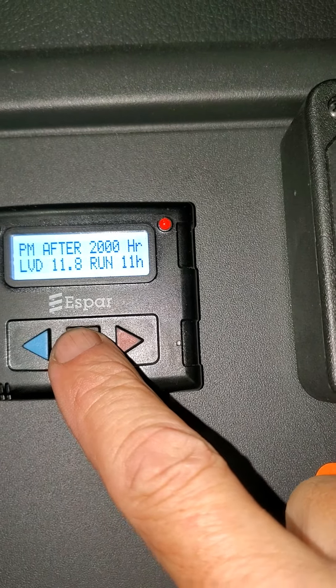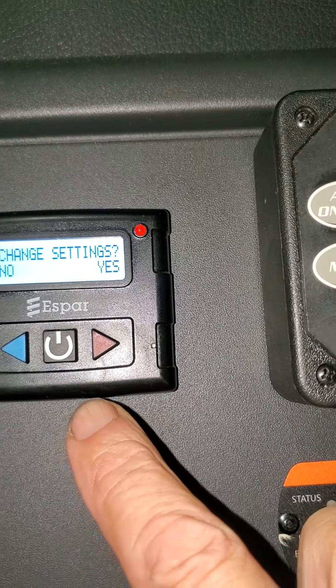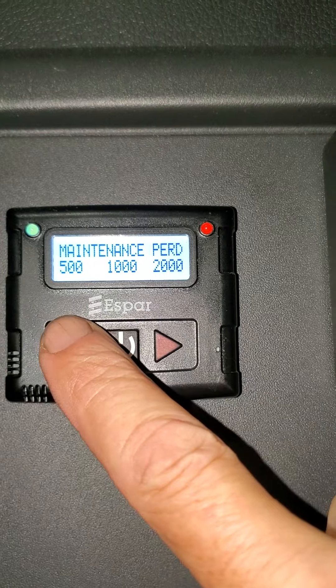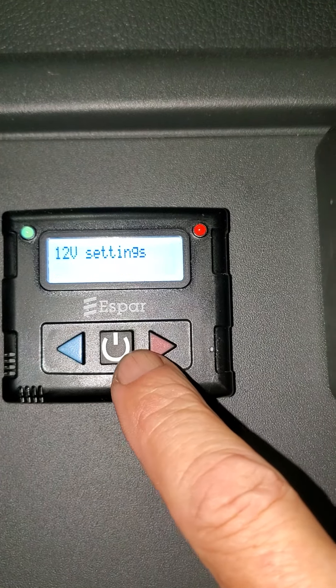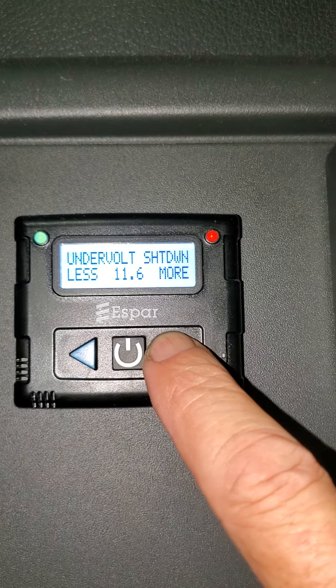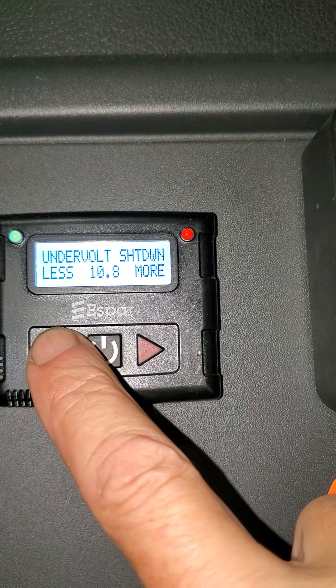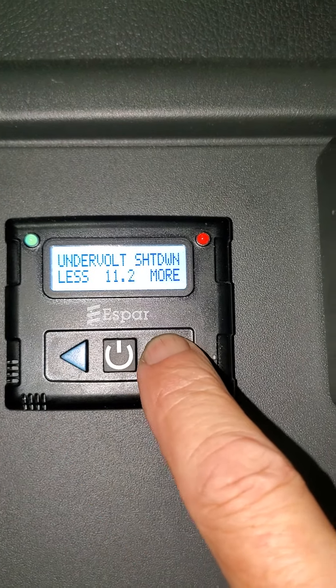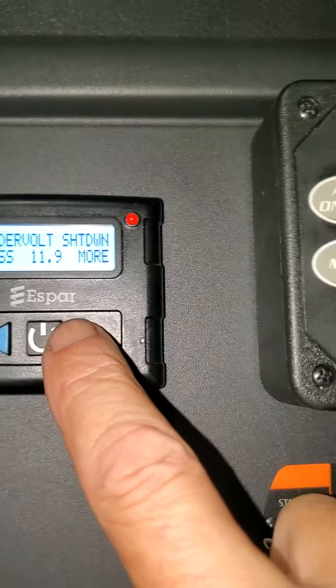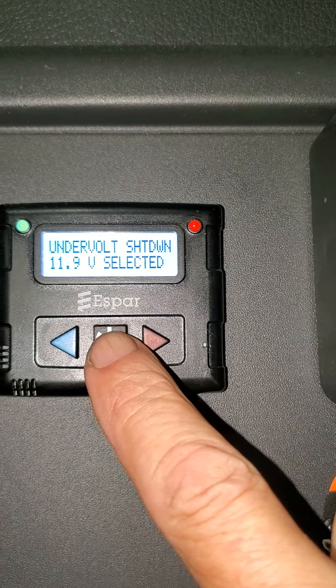Current settings — as soon as that comes up, you want to hold the button in and release it. Change settings? Yes. Maintenance period — you could do 500, 1000, or 2000. I'm going 2000. I can press the button. Under voltage — I want to go more. Instead of 11.4, I'm going to set mine at 11.9. I can press the button, or I can just wait a second and it'll change. There we go.